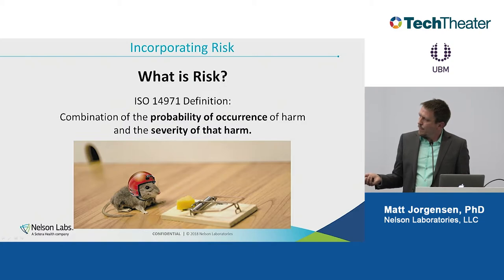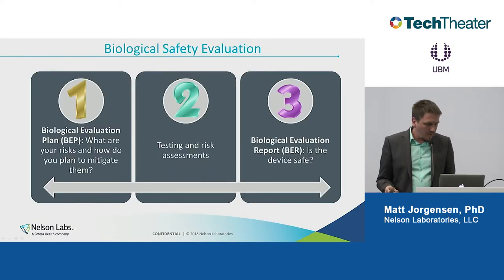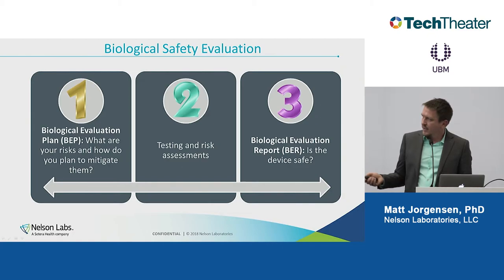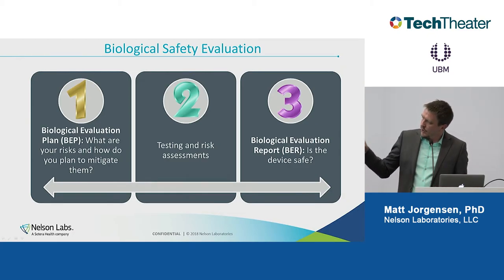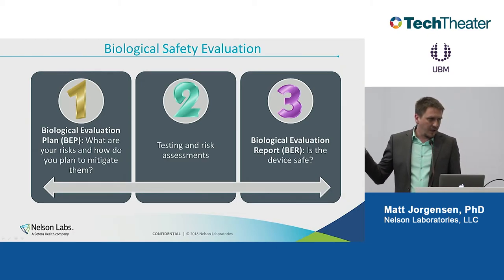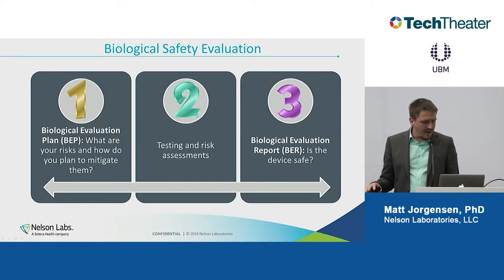So what I just read, the quote from the FDA, it really points us to a flow like this when we approach biocompatibility. We should have some sort of biological evaluation plan. This is the document where we look at the device, its intended use, what materials are there, and we identify those risks that it presents. And then we prescribe a strategy to address those risks.